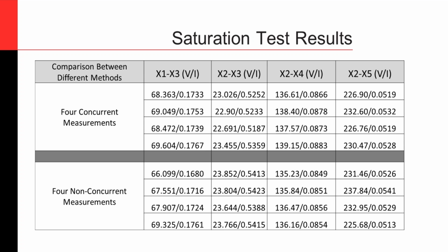So to answer your question directly, our software does not tell you whether it is a good or a bad CT. It just gives you the result. It also gives you the parallelogram. It also gives you the ratio correction factor based on the test you do on a metering type CT. But it does not explicitly tell you, hey, this is a bad CT. You can determine based on the results you saw from the CT.